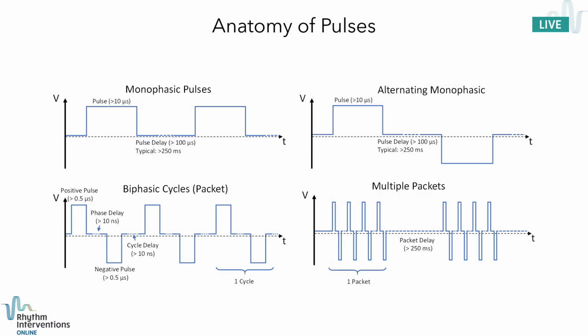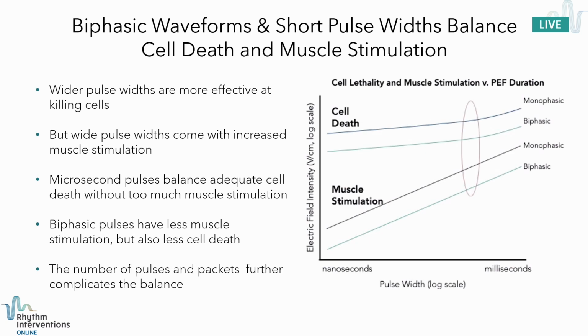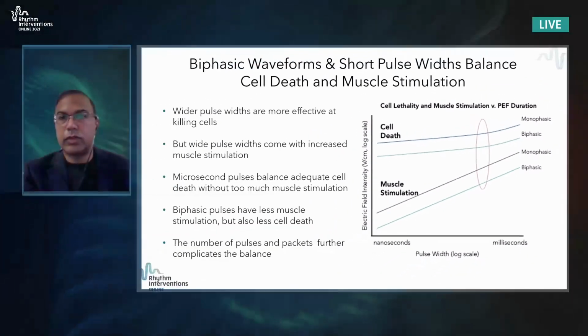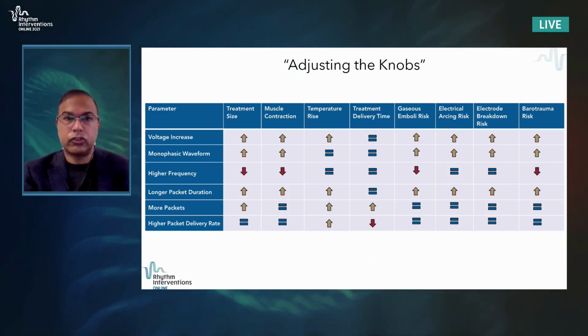So if we look at the anatomy of pulses, we can use either a monophasic or biphasic type of pulse wave. And then again, we can deliver them in multiple packets. In general, most of the systems are using biphasic waveforms as opposed to monophasic waveforms, because as it turns out, you can use lower powers with biphasic pulses. Compared to monophasic pulses, the biphasic can give you much less muscle stimulation and the same amount of cell death, but at a lower power. So it's a way of being able to optimize delivery without getting the problems of a so-called large charge.